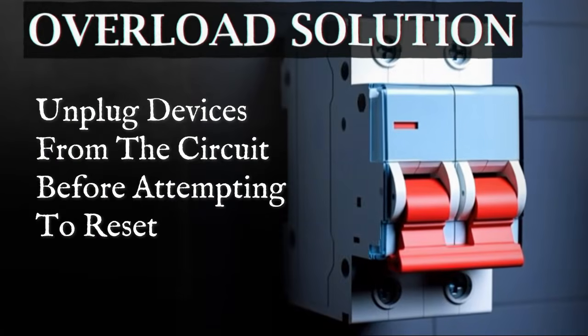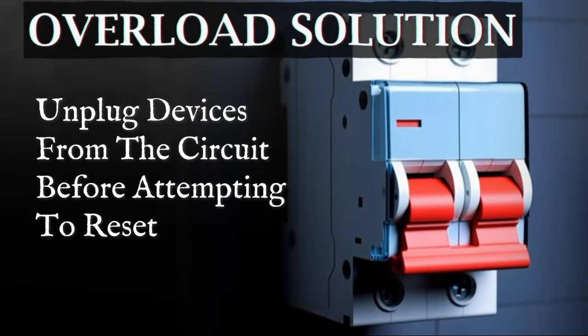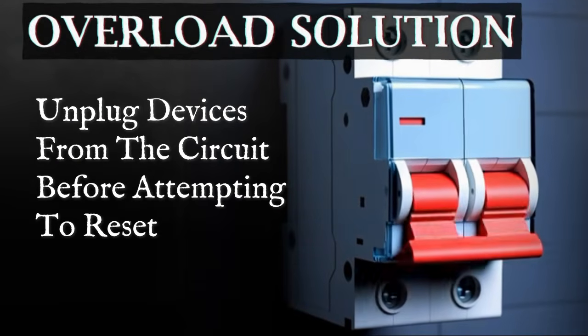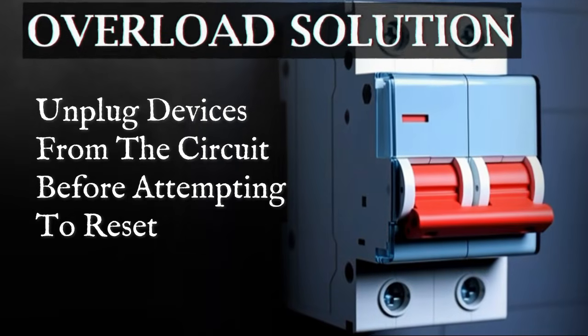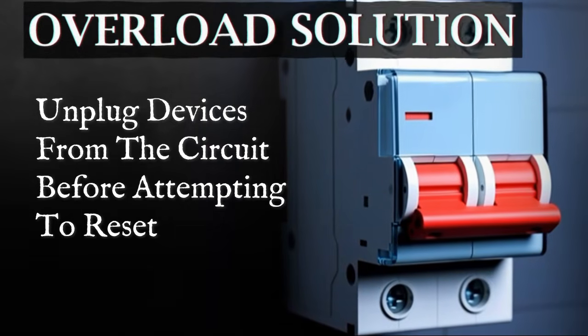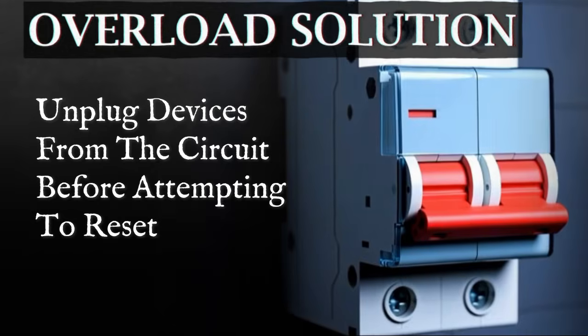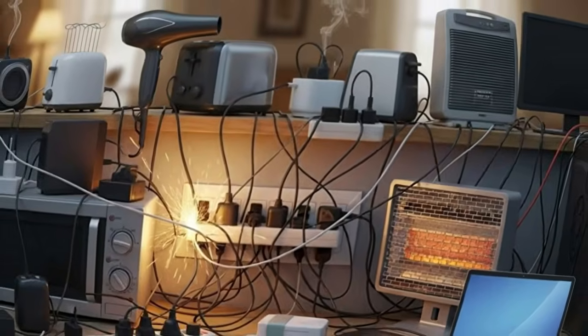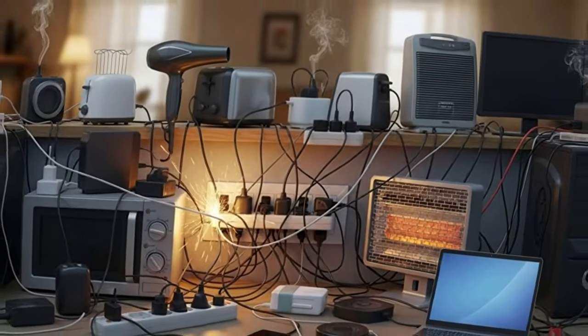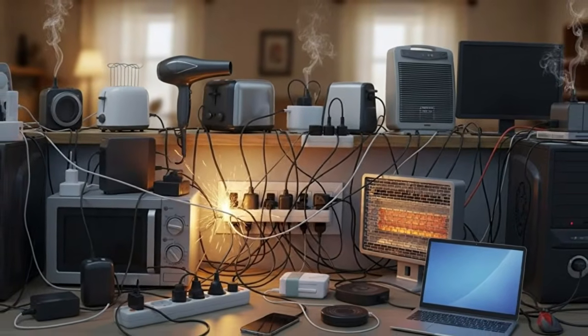The solution for an overload is straightforward. Unplug devices from the circuit before attempting to reset. If the breaker resets and holds with reduced load, you've confirmed an overload condition. You'll need to redistribute your devices across multiple circuits or have an electrician add additional circuits to handle your power needs.